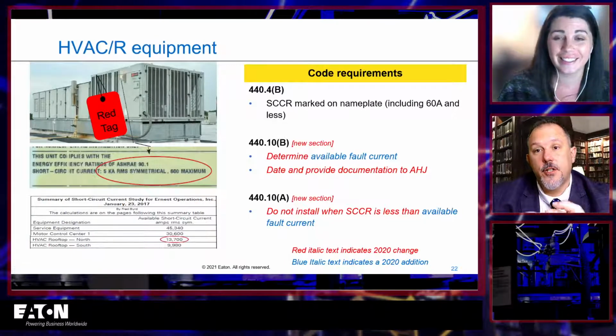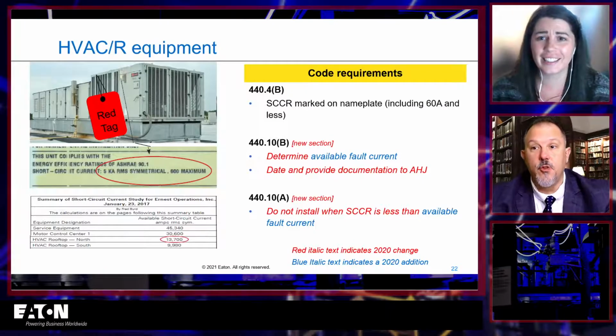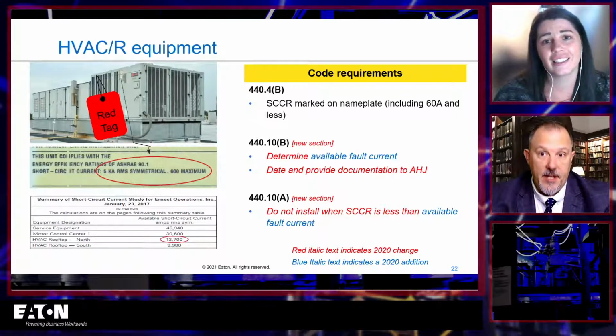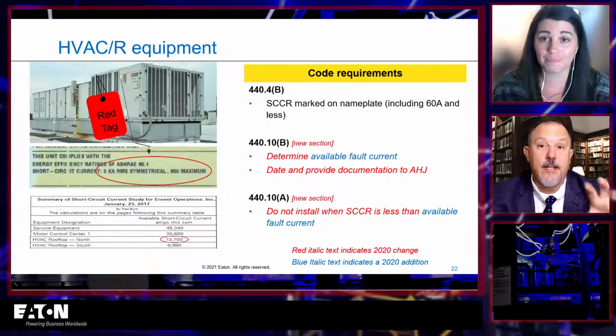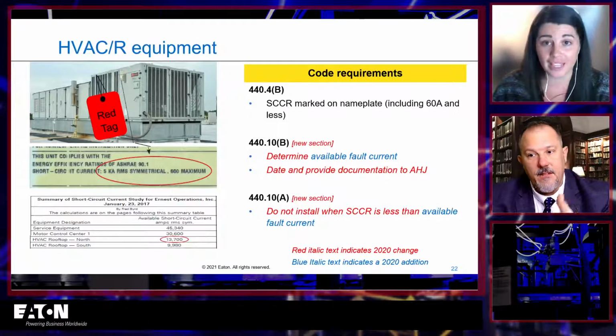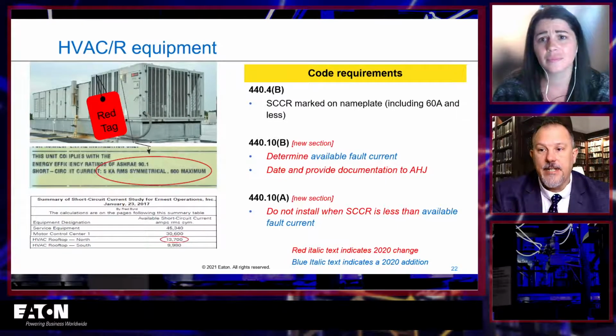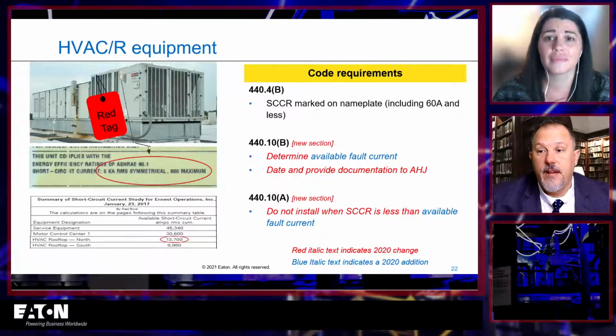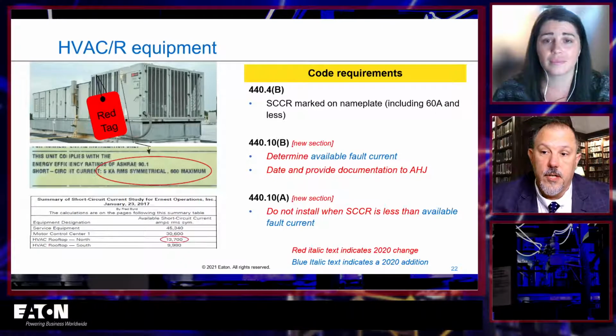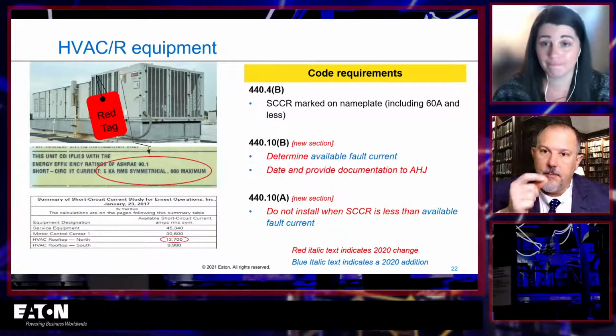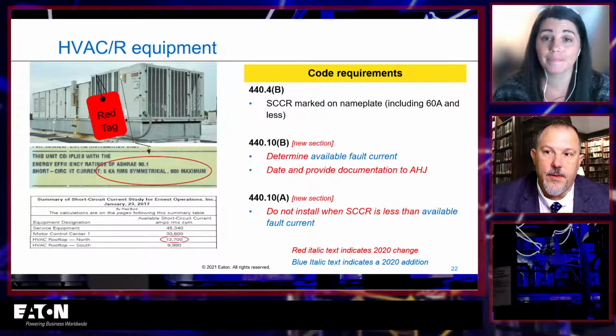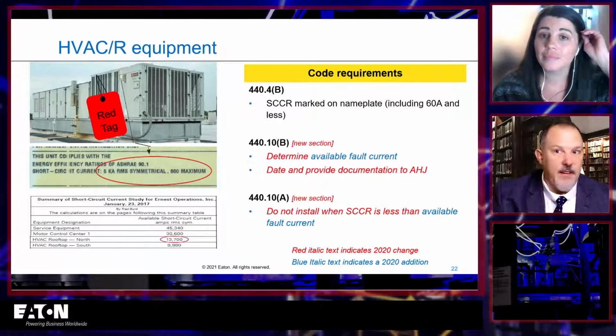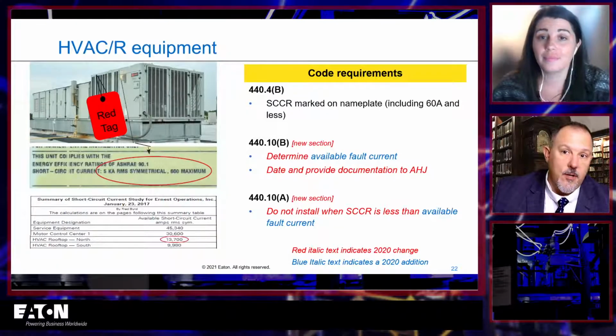And Shreesh was asking, do terminal blocks affect the short circuit current rating? And I believe you're going to get into that, but they definitely can. And then Vinny pointed out that contactors and other components similar to contactors could have an integrity issue after the fault due to the stresses on all those. Think about those contactors that are in there, but terminal blocks are definitely listed with upstream overcurrent protective devices, and I know you're going to get into all of that.